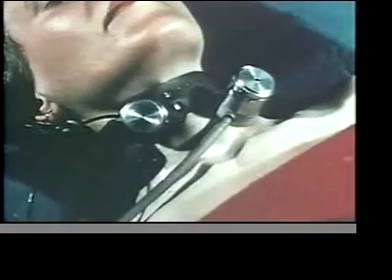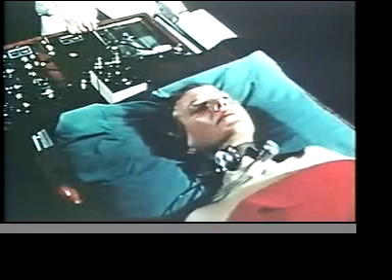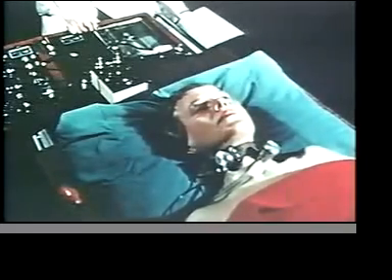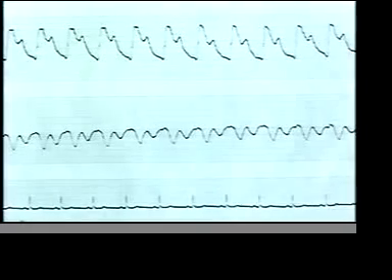In modern instruments developed from the polygraph, the receiver is usually a carbon microphone. Electrical transmission eliminates time lag. Thermionic valves provide suitable amplification, and the recording systems are similar to those used for electrocardiography. The phlebogram may be timed against the simultaneous arteriogram and electrocardiogram, as shown here on the Sanborn Polyviso. A phonocardiogram probably makes a better reference tracing.